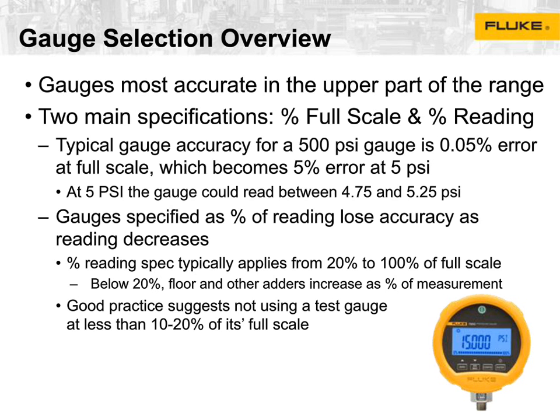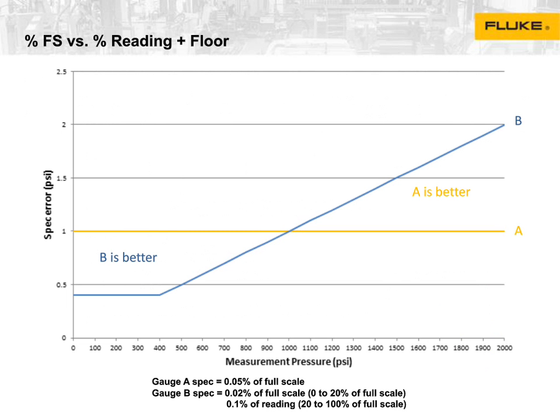So here's a graphical representation of that same discussion. These are two actual gauges made by two different manufacturers, and I'm not going to go into who's got what because this isn't a product comparison. It's designed to show how this concept works. You can see the yellow line is gauge A, which is specified as percent of full scale, and gauge B is specified with a floor as a percent of reading. What's interesting is that I happen to know these two gauges use the exact same internal sensors, so this is simply a choice of how the manufacturers chose to specify them differently. And you'll notice that right at 1000 psi, or 50% of the range, they cross in terms of accuracy.